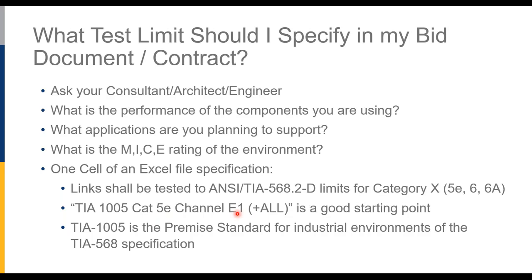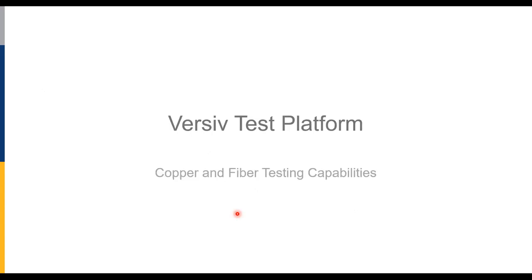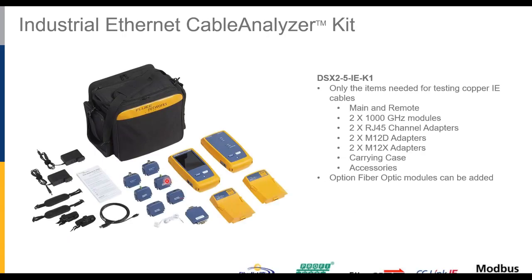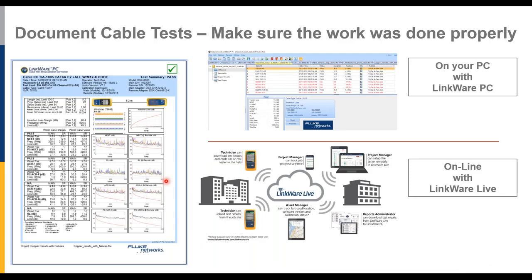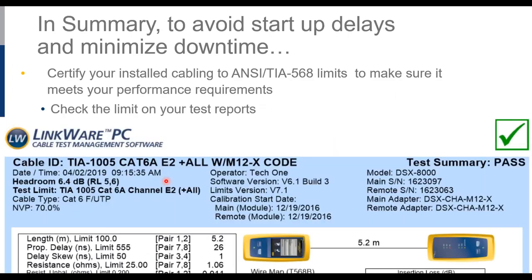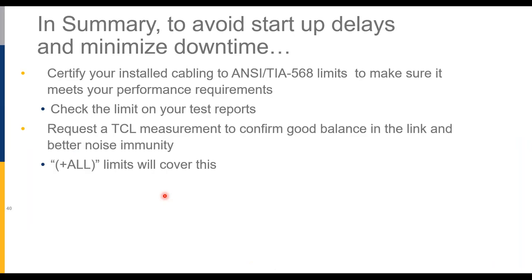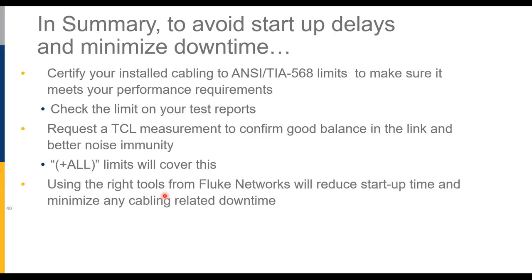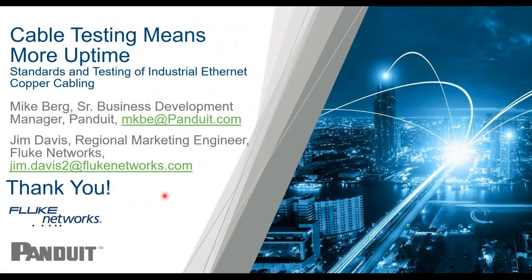Fluke Networks makes a tester with an industrial version that has M12 D-code and X-code adapters. Make sure you ask for the test results — they show your cabling has been properly installed. In summary: follow the standards, check the limit on your test report to confirm they tested to what you asked for, TCL measurement will confirm your system is well balanced with good noise immunity, and using the right tools and cabling will reduce startup time.